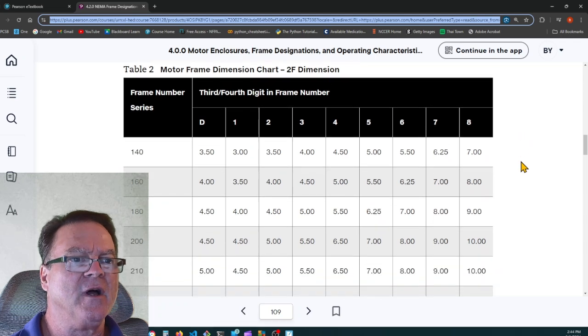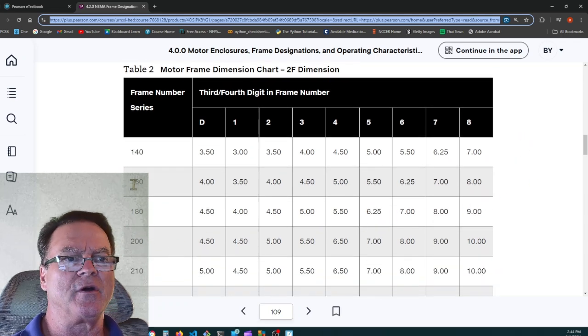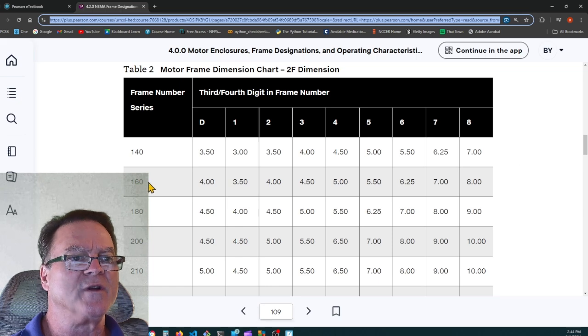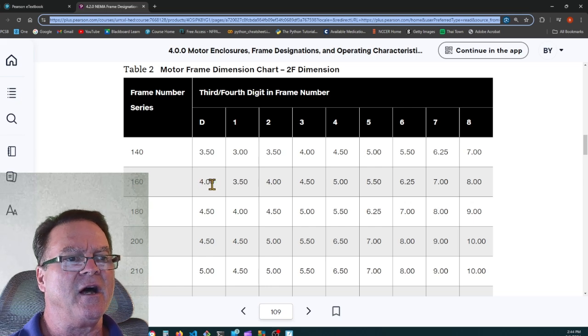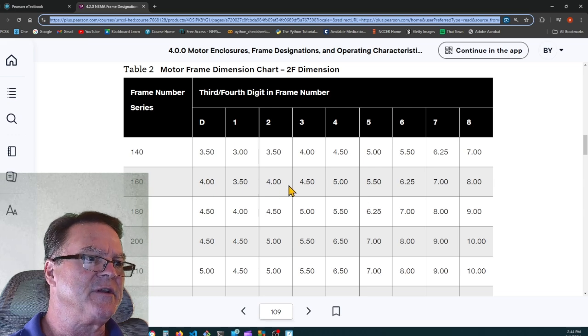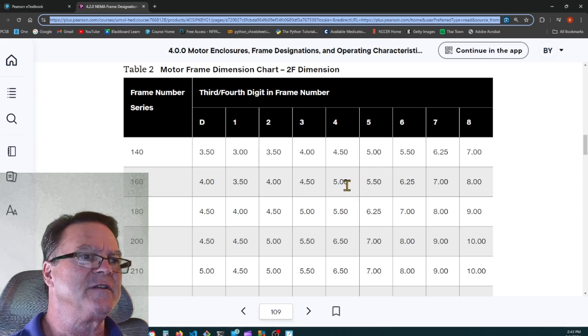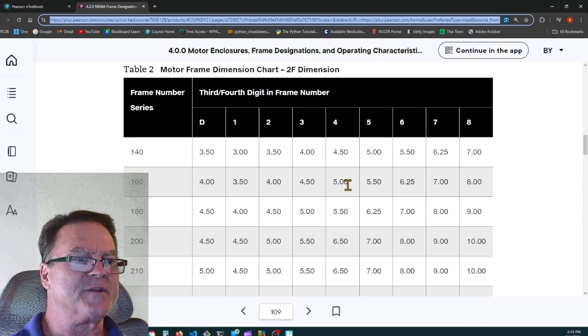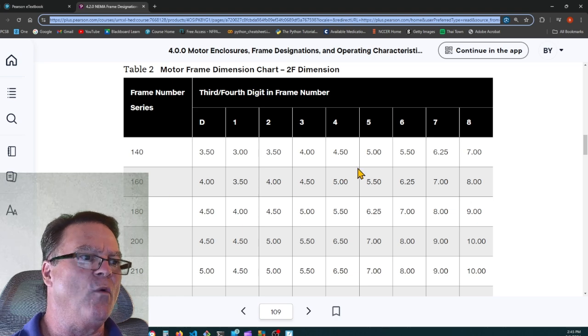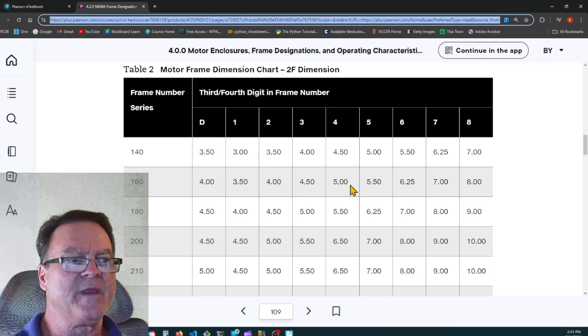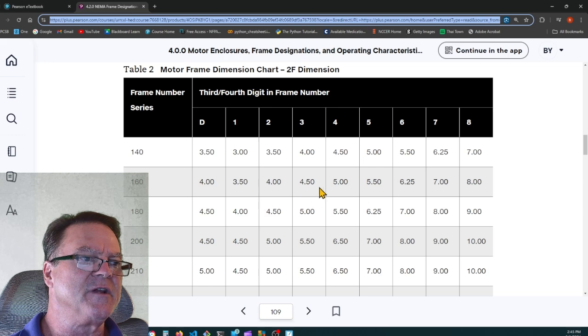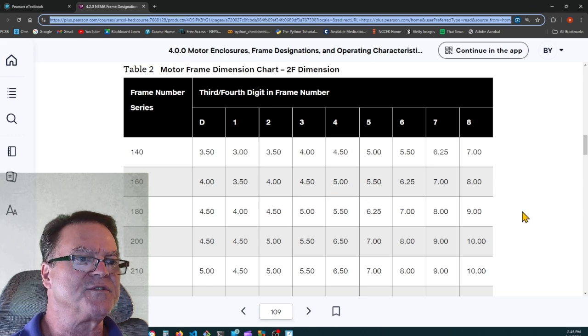Let's look at an example. Let's say the first two digits are 16 or 160. It's the 160 series, but if the first two numbers are 1 and 6, then the D dimension from the feet to the center line of that shaft is 4 inches. And then the third digit is going to be the 2F dimension. And if you remember, that was the dimension between the bolt holes, the center of the bolts. So let's say it's 164, then it's going to have 5 inches between those bolt holes. So 4-inch D dimension and 5 inches between the bolts.